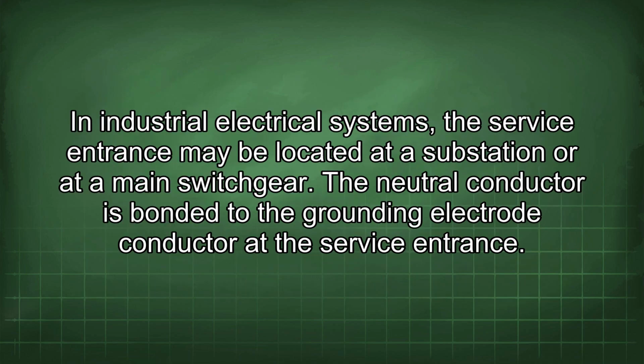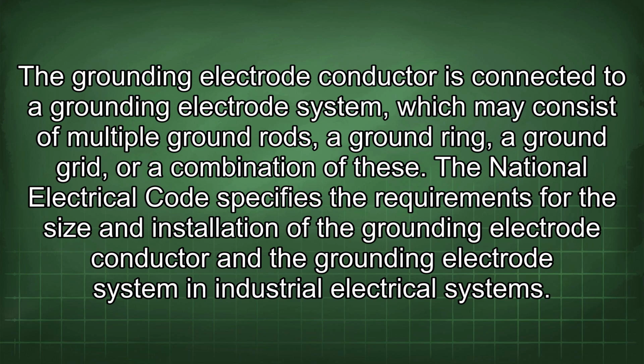In industrial electrical systems, the service entrance may be located at a substation or at a main switchgear. The neutral conductor is bonded to the grounding electrode conductor at the service entrance. The grounding electrode conductor is connected to a grounding electrode system, which may consist of multiple ground rods, a ground ring, a ground grid, or a combination of these. The National Electrical Code specifies the requirements for the size and installation of the grounding electrode conductor and the grounding electrode system in industrial electrical systems.